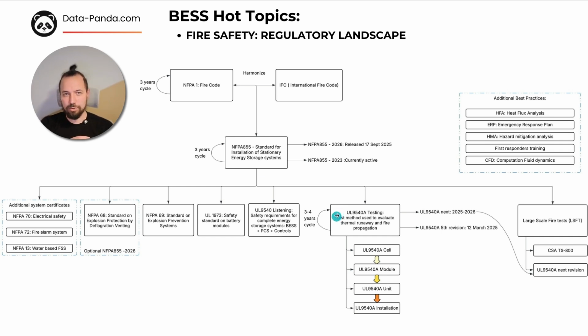Now let's come back to UL 9540A. First of all, it's not a certification, but a test method used to evaluate thermal runaway and fire propagation in battery systems. So generally UL 9540A is considered proof of battery energy storage compliance with NFPA 855. So it's a method of testing and not a standard. You will not get a certificate, you will just get test results. And testing is performed at 4 levels. First of all, cell level, then module level, then unit level, and the last one, installation level. But on the installation level, we do not always do this testing.